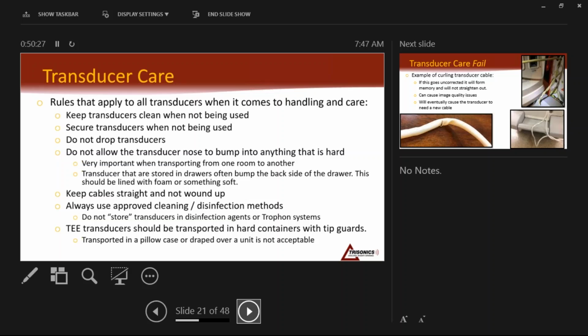I usually get the phone call Monday morning. So how long is too long to leave the probe soaking in Cidex? And my answer is usually, so it's been there since Friday, right? And they're like, yeah. And that doesn't necessarily kill the probe, but we do believe it takes life out of the probe. So instead of that probe lasting 5 years, from that event, maybe it only lasts 4.5 or 4 years. You do that a few times, and it will keep reducing the length of the life of that probe.